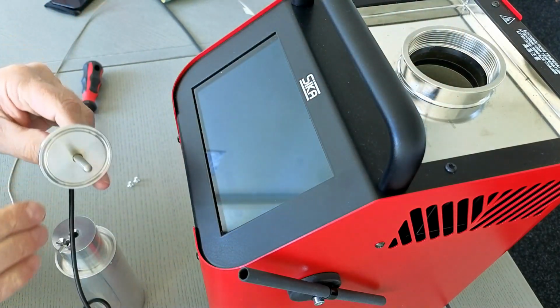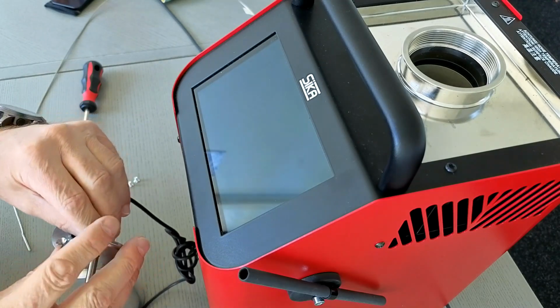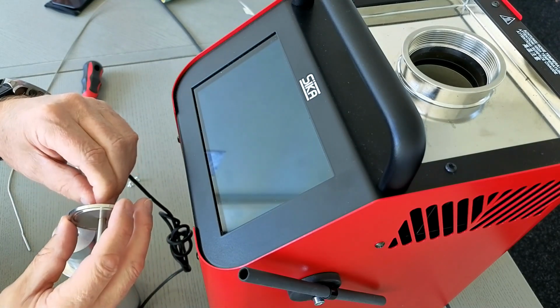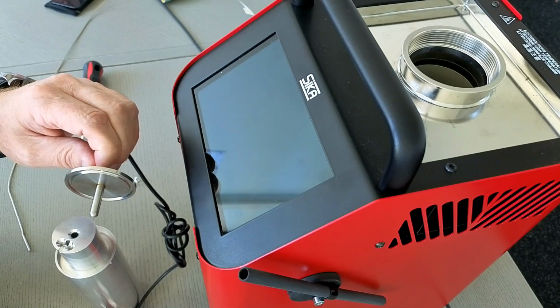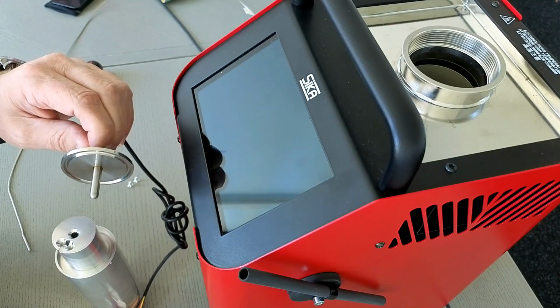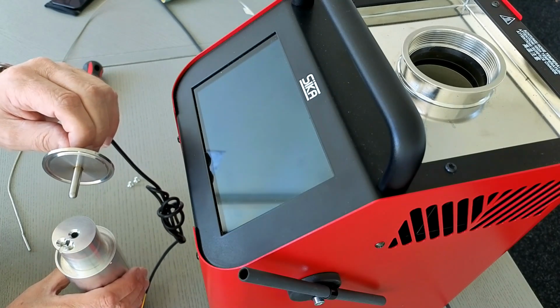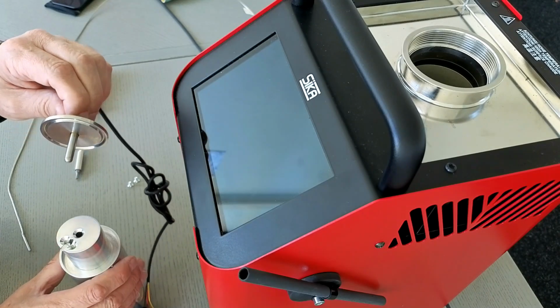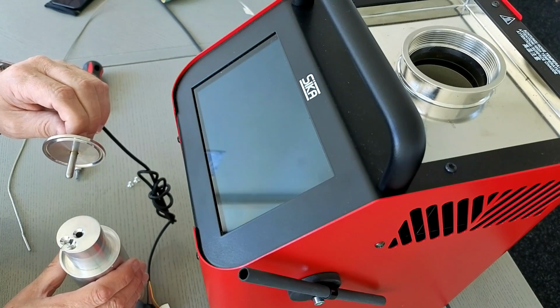But you can imagine that if you have liquid around the sensor, you get different calibration results. So instead, I like to do this with a dry block calibrator.